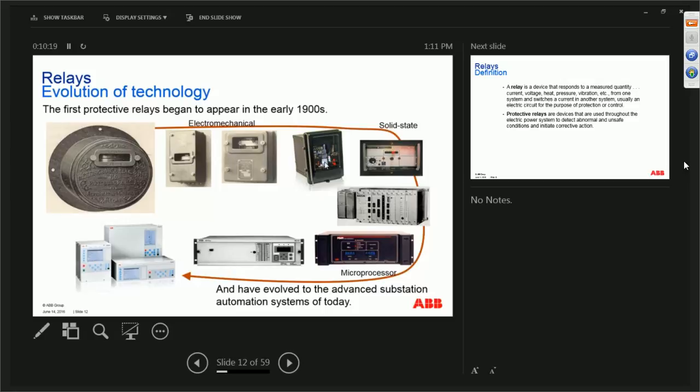Well, that was the 1980s, and now it's 2016, and some of these first-generation microprocessor relays are failing now. They've been in service for 30 years, and now people are calling up and asking why these are failing. And I'm saying you got 15 more years of life out of those than I thought they would to begin with. So they'll fail eventually, but they have a very good track record. At least they let you know what their health is and if they're imminently going to fail.